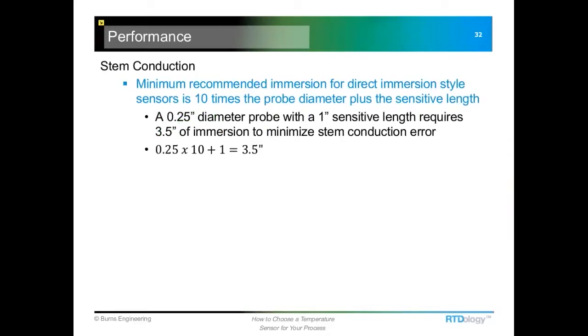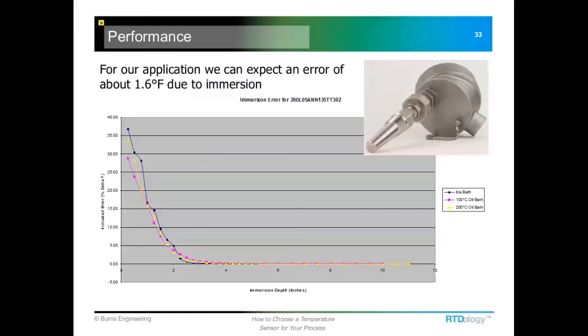So when we have a direct immersion style sensor, to overcome this stem conduction, we like to have 10 times the probe diameter plus the sensitive length. That ends up being about 3.5 inches. Most of the sensing elements are about 1 inch long, with a 1/4 inch diameter probe, and just going through the math there, we end up with 3.5 inches. And that we found is a good rule of thumb. It doesn't work for everything, but for most liquids it will work okay. For air temperature, you typically would need more immersion, and I'm guessing it is probably even twice that would be necessary to really get away from all of this stem conduction. Now, for our application, we're using a probe and a thermal well.